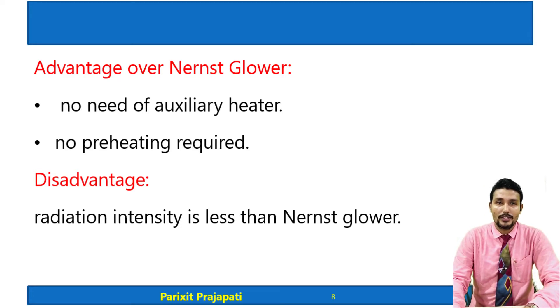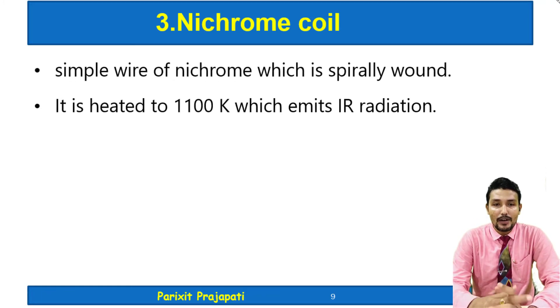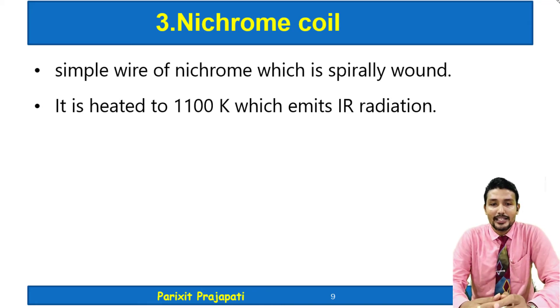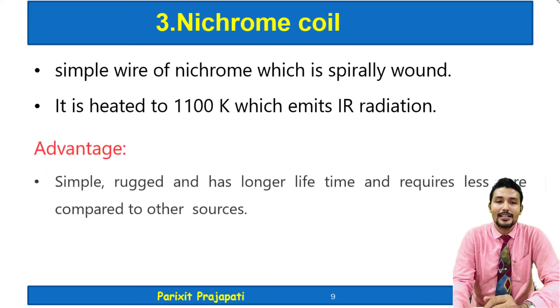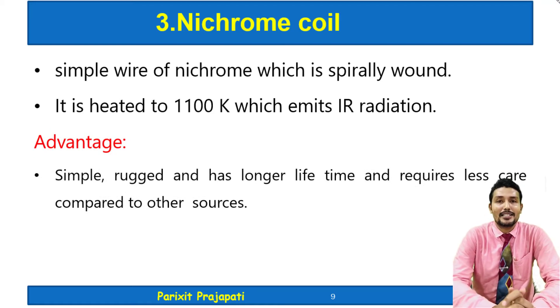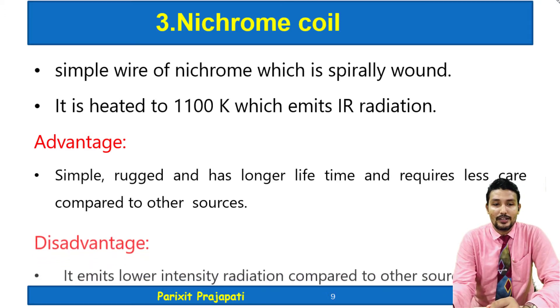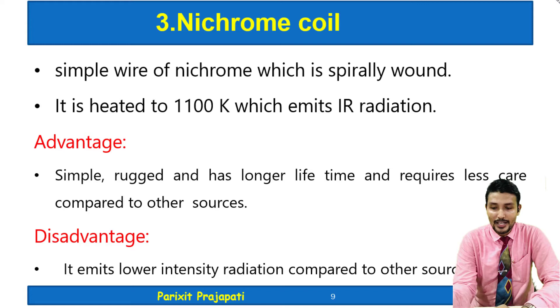The Nichrome coil is a simple wire of Nichrome which is spirally wound and heated to 1100 Kelvin, emitting IR radiation. Its advantages are that it is simple, rugged, has a longer lifetime, and requires less care compared to other sources. Its disadvantage is that it has low intensity IR radiation compared to other sources.